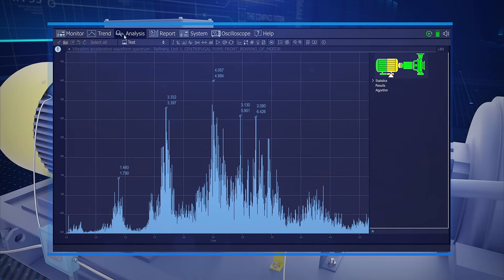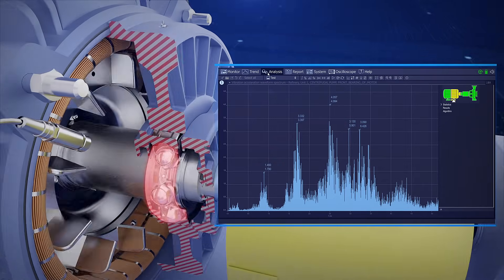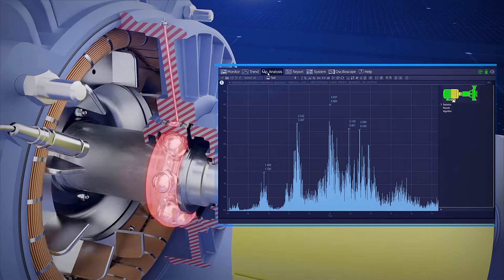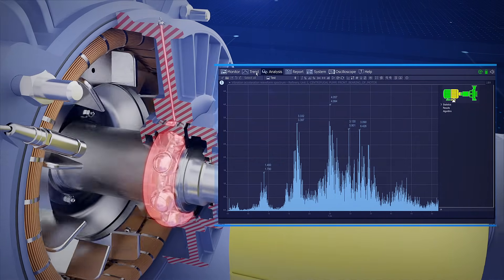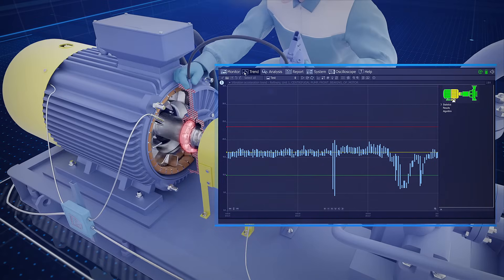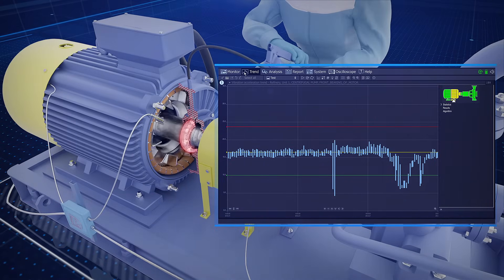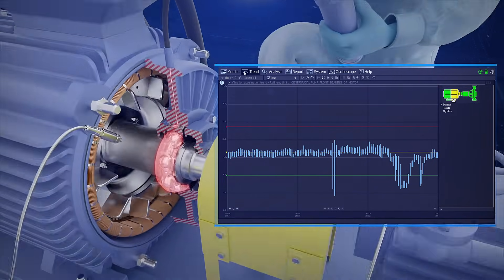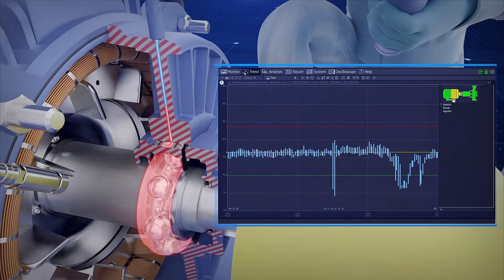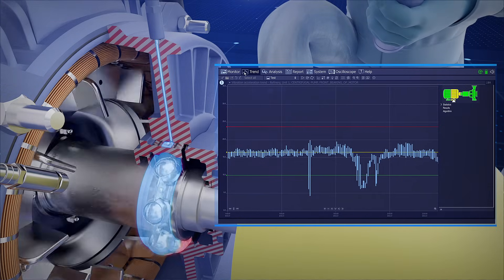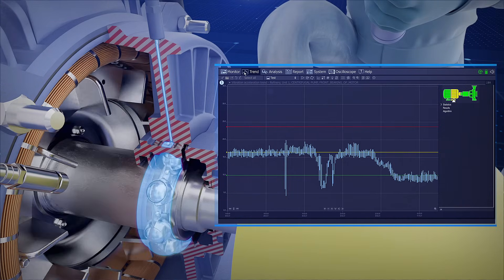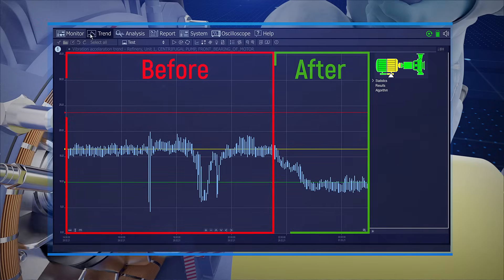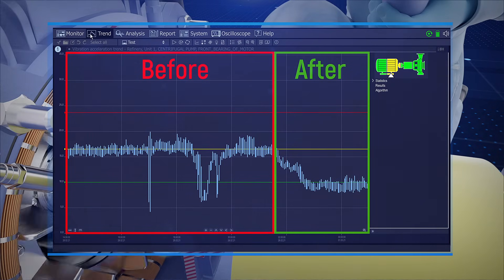Oil starvation of the front motor bearing was due to the discrepancy between the applied lubricant and the required temperature range. After the reliability department investigated the motor cooling problem and replaced the used lubricant, the vibration activity of the machine decreased and its state of health settled down in the acceptable area.